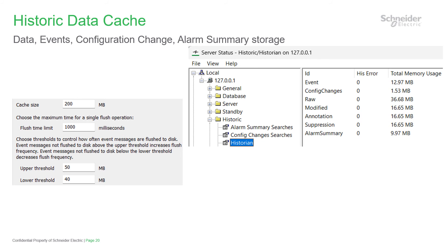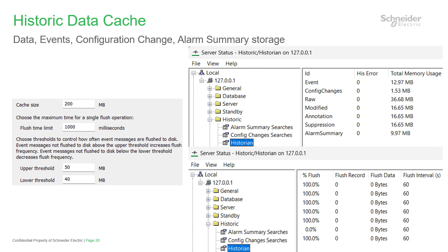The flush time limit parameter controls how long the server will pause to write historic data. During this time the database is exclusively locked. You shouldn't need to change this setting as longer flushes may be noticed as pauses in client operation. Finally, the upper and lower thresholds control the dynamic changes to the data flush frequency. These numbers should be about 20% different from each other. Making them too small will cause additional flush and disk activity; too large and the server shutdown time will be extended. You can adjust these settings during server operation and check their effect by looking at the flush interval, which should remain at 60 seconds and only dip below periodically.